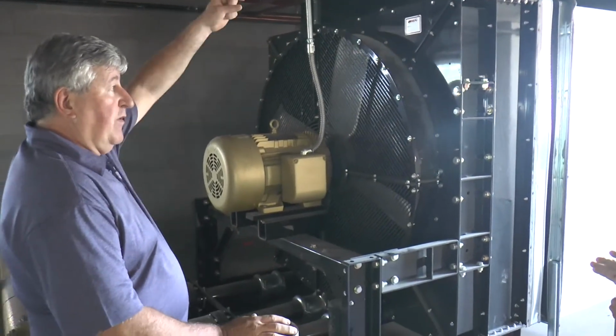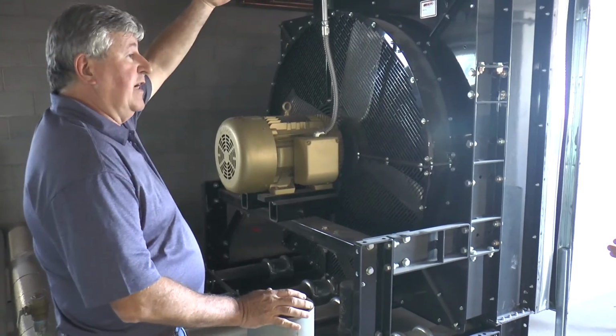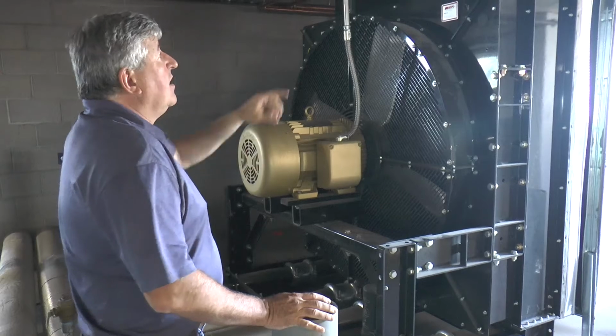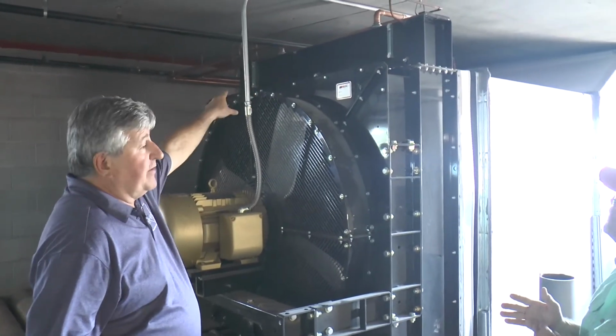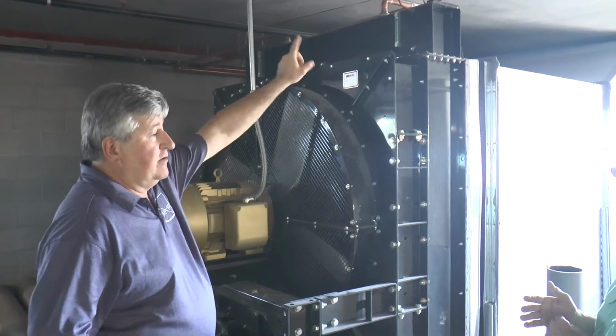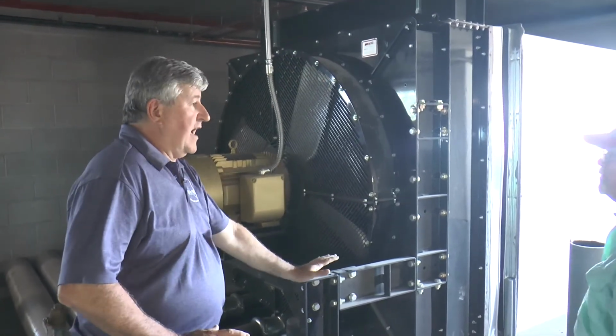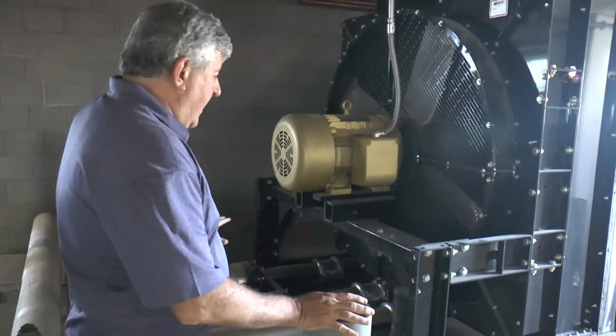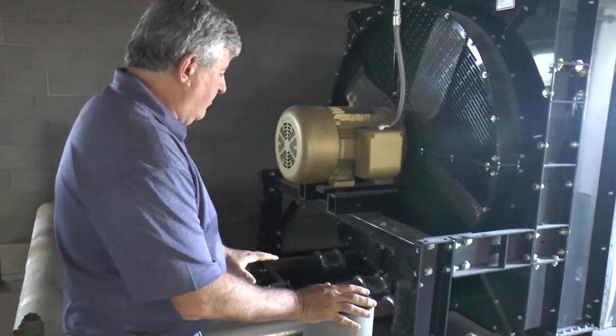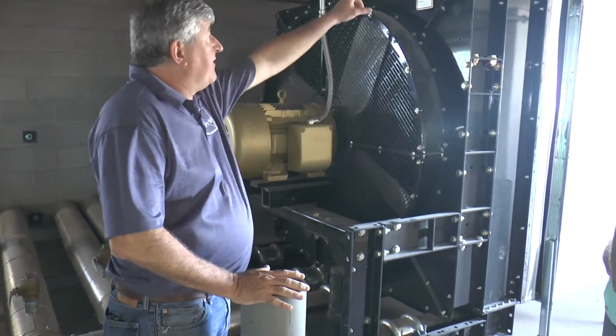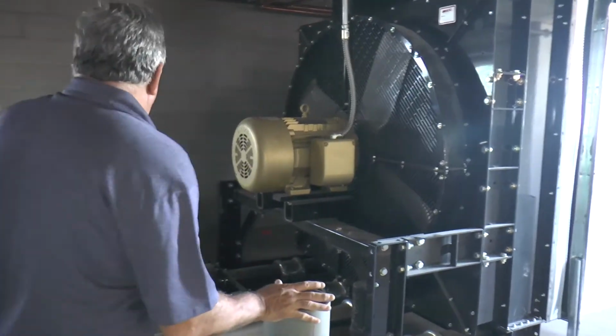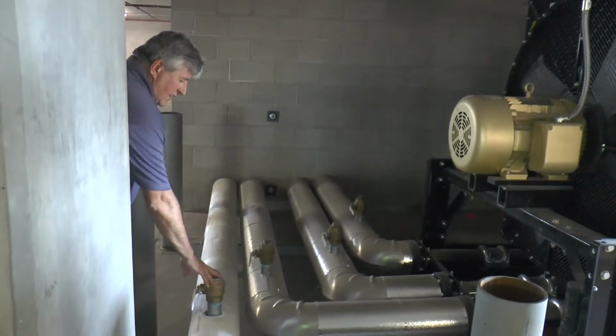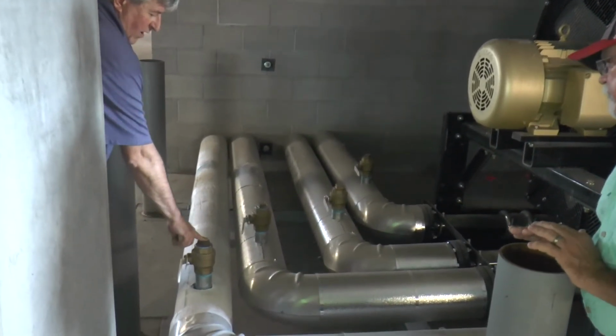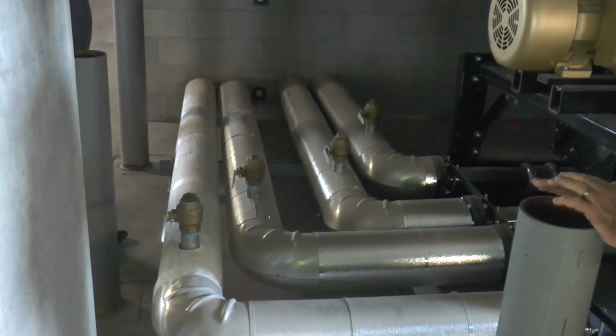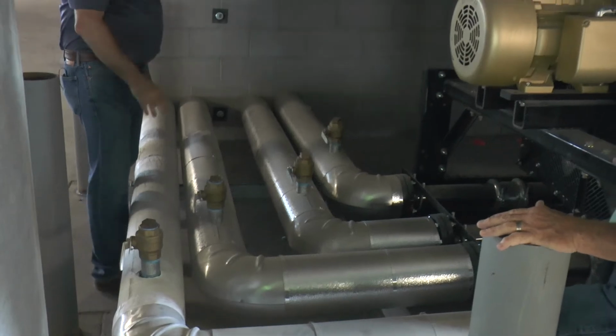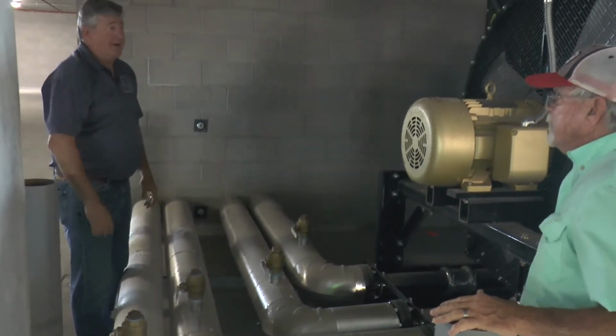Also, there's a surge tank 1 more floor up. Because of the ceiling height in here, we had to relocate the surge tank 1 more floor up, and it's plumbed down. Top of the line is the makeup water line for both tanks and the air line to bleed the air out of the system. Since this is the highest point of the system, any air bubbles that are in the system will gravitate to there and bleed out the surge tank. On this side, we fill the system up using water here, and then once this was filled, then we filled it up from the surge tank upstairs. Since this is lower than that, if you open this, we'll have coolant everywhere.